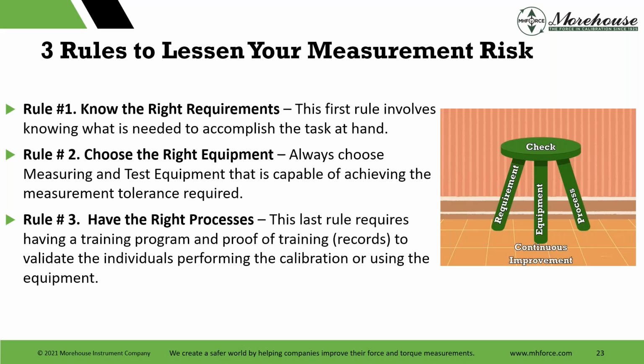So rule number one, right requirements: knowing what you need to accomplish the task at hand. Rule number two, knowing the equipment. You choose measuring and test equipment that is capable of achieving the measurement tolerance required. If you want to calibrate something that you want to know is good to 0.1%, you should buy something that's better than 0.1%. And rule number three, have the right processes. This requires having a training program and proof of training to validate the individuals performing the calibration or using the equipment. This would also help you develop your procedures.